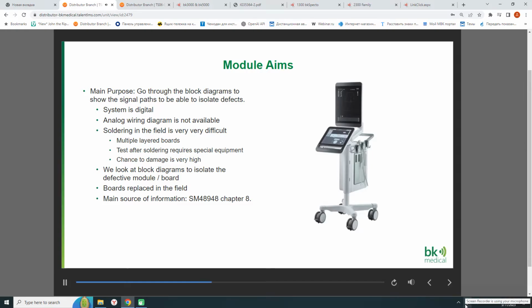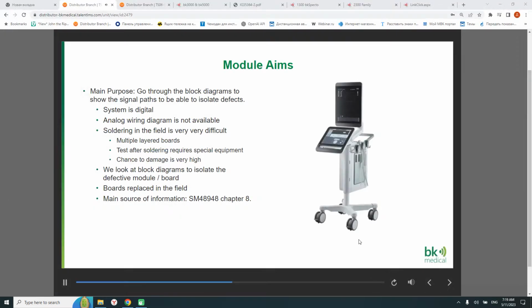In addition to this, the chance of damage is very high. It's actually much, much more likely that you will damage the board rather than making a successful repair. So instead of talking about analog wiring diagrams, we would like to split the scanner up into blocks. So we look at a block diagram instead. Then you can isolate the defective module or board if you know where a function is taken care of.